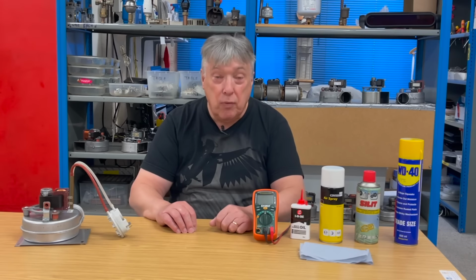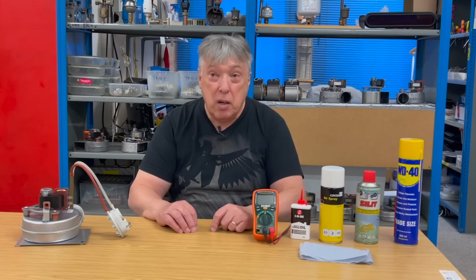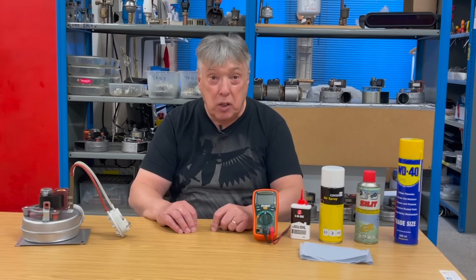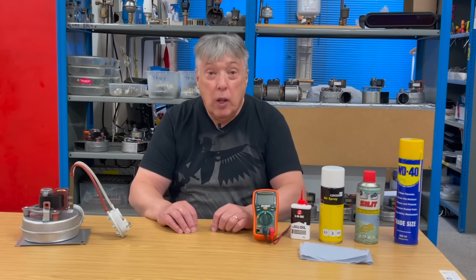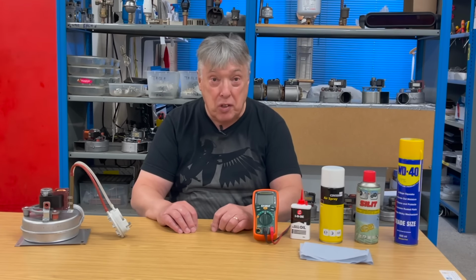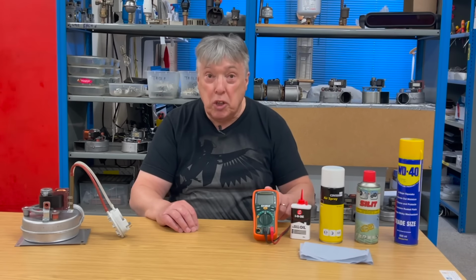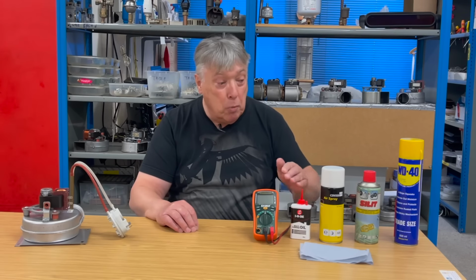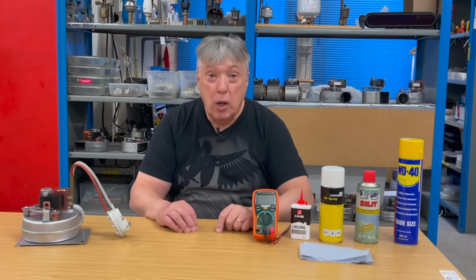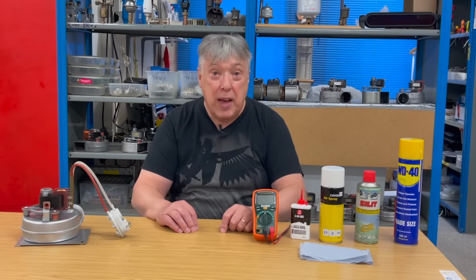But we also need to find out whether the fan needs changing. So that's going to be around a year, 5 years old, 6 years old, 7 at the latest. It needs updated to the latest version, or it's not been maintained correctly and it's now seized up or about to seize up, and how to solve that problem. So we're going to need a good auto-ranging multimeter. We're going to need some lubricants. Some of these are good, some of these are banned, for example. So first of all, let's have a look at the two different types, the single speed fan.